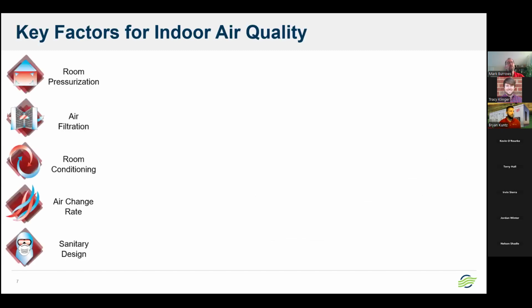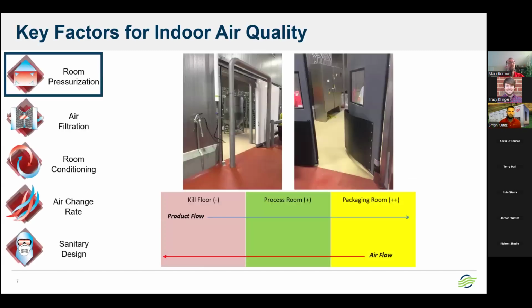So diving into the 5 key characteristics of our units, I mentioned room pressurization, and this is super critical for those that have ever been on a kill floor or a harvest room or evisceration. I mean, these are very, very dirty environments. And if that's butted next to a process room, you absolutely need to make sure that your process room is properly pressurized. If it's negatively pressurized and you're sucking in the atmosphere from that kill floor, you are certainly at risk to see exposure to contamination.